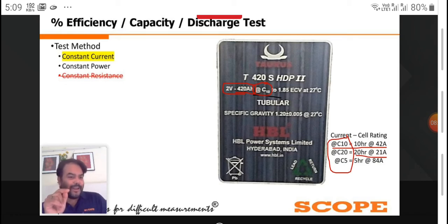But these batteries, whether it is lithium ion or any other, even the most modern battery, LiFePO4, lithium iron phosphate batteries, even they are not maintenance free. They have maintenance schedules. You need to do the other maintenance, but you need not put in the electrolyte, because you do not have that option. That's the point it was told as maintenance free. There is nothing other than that maintenance free.